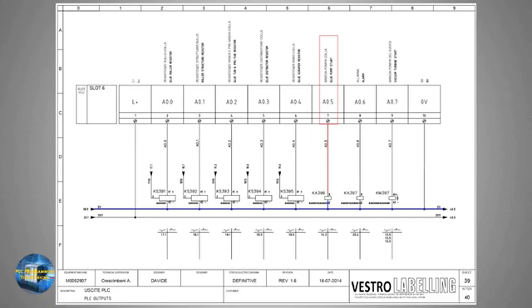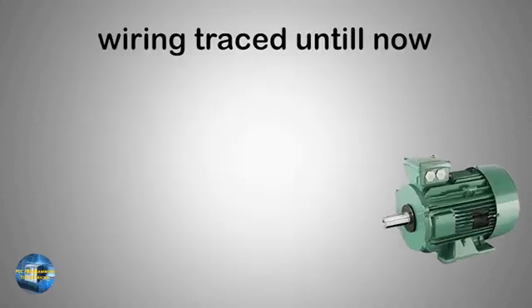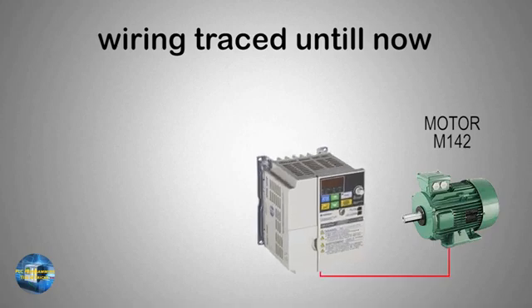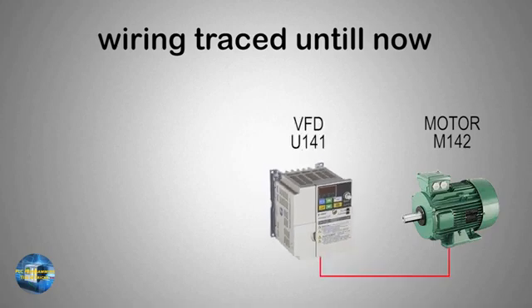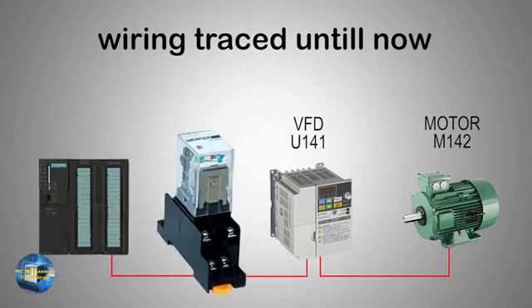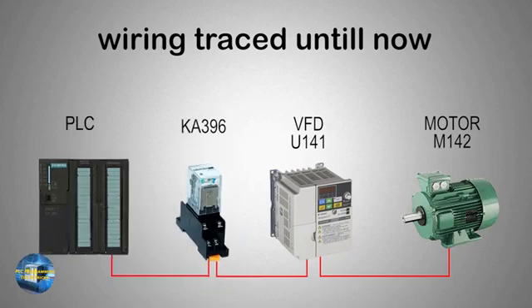So now we know that the motor M142 runs through a VFD with tag U141, and its VFD gets the run command signal from the PLC via relay KA396, and this relay is turned on by the PLC digital output A0.5. Next, we will come back to sheet number 14.